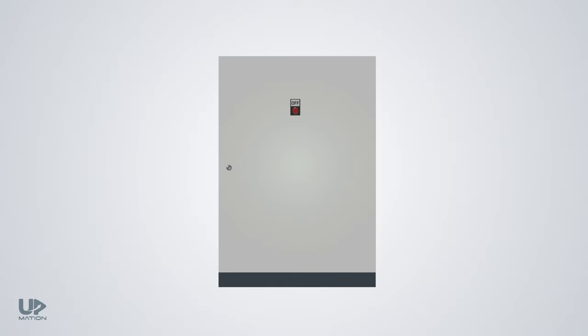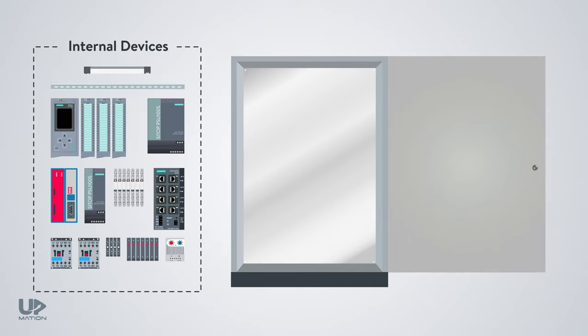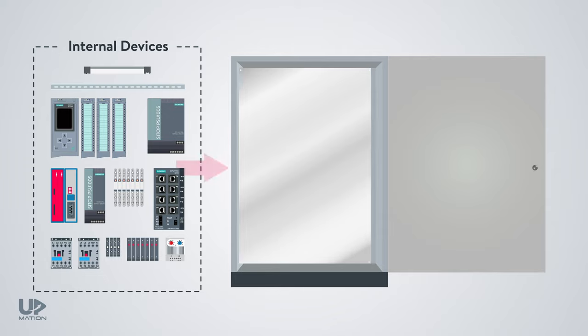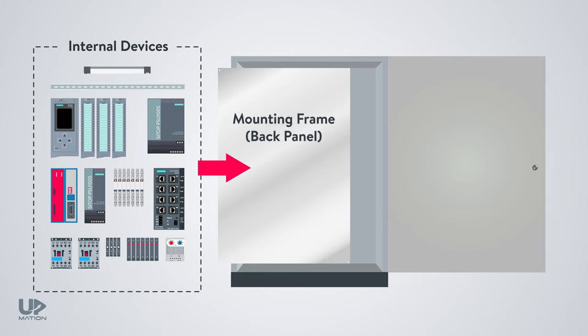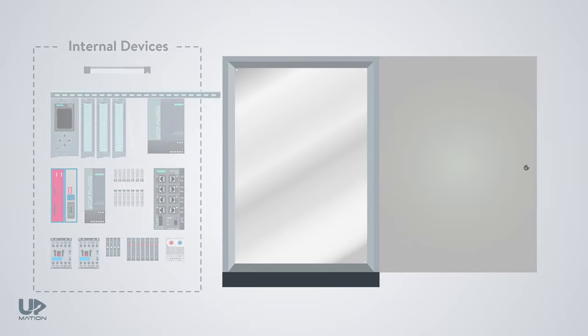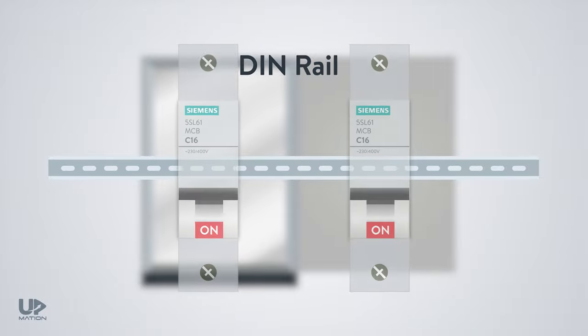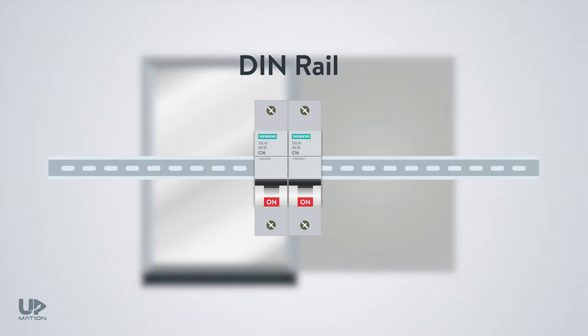The first is the enclosure, which houses our internal devices. I'll explain more about the enclosures in a future video. The internal devices should be installed on a thin metal sheet called the mounting frame or back panel. The first piece of component to install on the mounting frame is the DIN rail. DIN rails are long metal strips with standard size and some holes in between that we need for mounting the electrical devices on them.